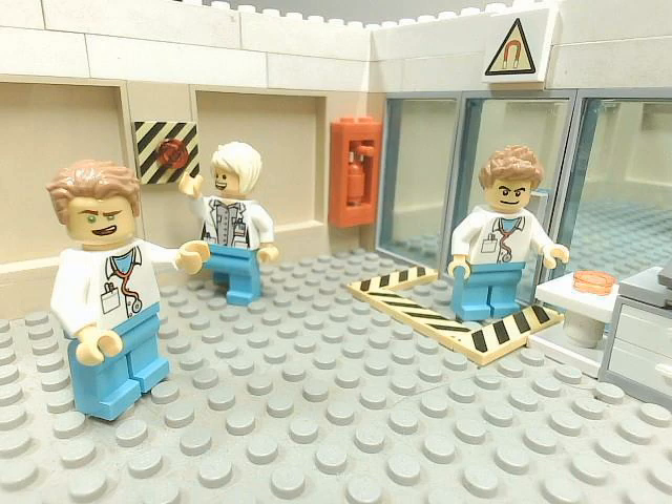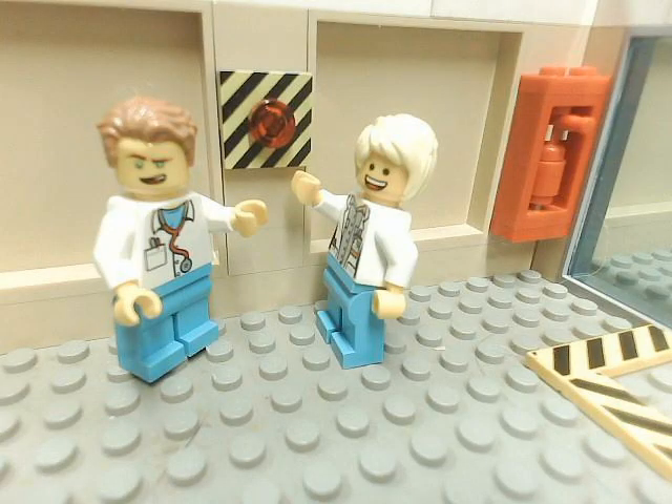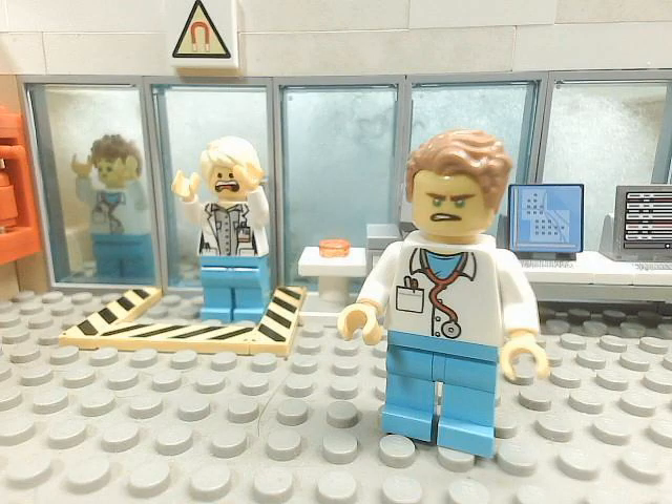There are always two emergency buttons at an MRI. One button turns off all electrical equipment and should be pushed if there is a fire — this button leaves the magnet on. A second button turns off the magnet, and should only be used if a life is in danger, as it can cause dangerous situations including displacement of all oxygen in the room or an explosion.